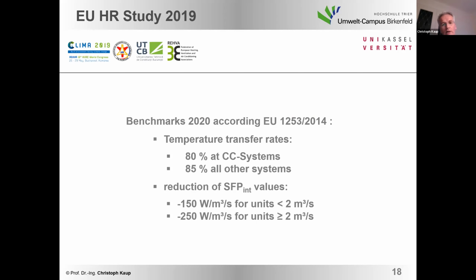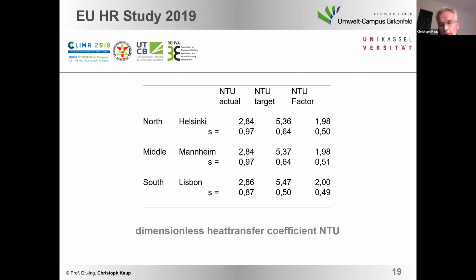And if you would like to reach them, comparing to the actual standard, we see that we have to double our amount of heat exchangers. That means we have here a factor of 2. That means we have to double our effort in heat recovery to reach these values. That means we have to install not, I don't know, 16 rows, we have to install 32 rows just to achieve these requirements if they would be the next step.